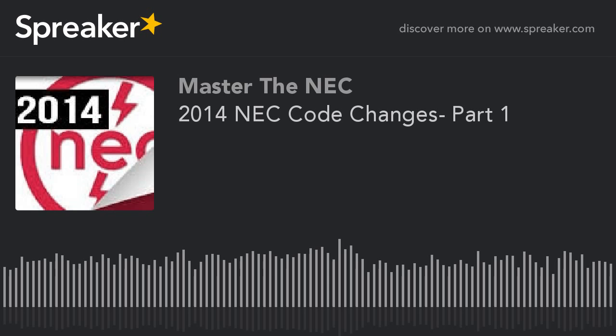Disconnection means for this Class 2 power, because again, once it switches over and starts going out to this grid, then we're looking at Class 2 power, and of course you're going to have Class 2 power supplies and all that kind of stuff. So there's a lot of guidance here. If you're into that type of system, then here's what we needed in the NEC, because that system is going to allow for the providing of low voltage AV devices, low voltage luminaire applications, electrical equipment that is actually low voltage. All could be powered, even some utilization equipment, different sensors for certain applications, can all be powered from this powered rail, this low voltage rail.